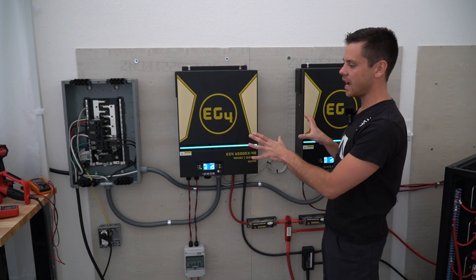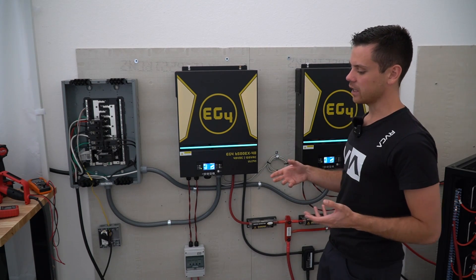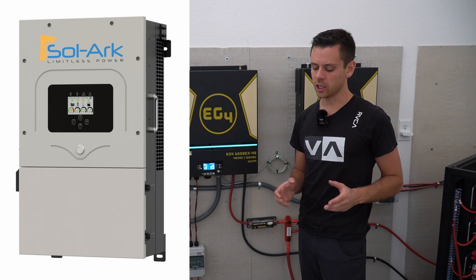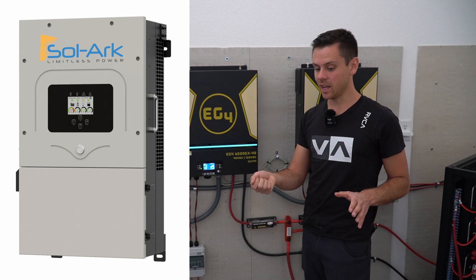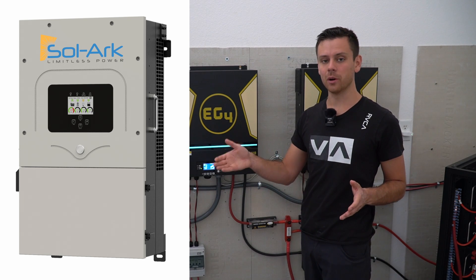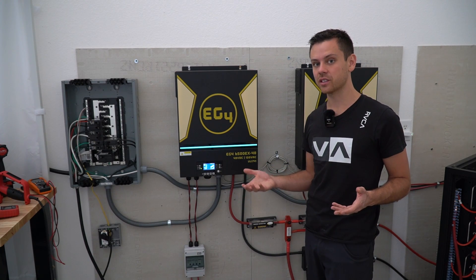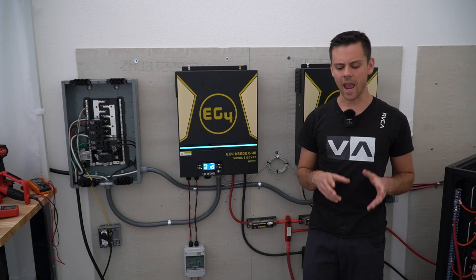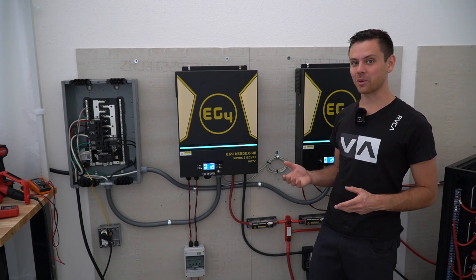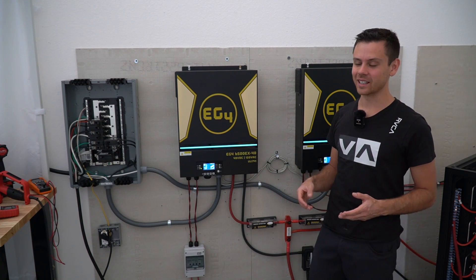For off-grid use, these are fantastic — I love every type of LV6548, including these. But if you want to pass inspection, you need to spend the extra money and get a Sol-Ark. You will have zero headaches: it has rapid shutdown, a transfer switch built in, and Sol-Ark's customer service has engineers that can remotely change the settings. The support, certifications, and UL listing are fantastic, and that inverter is approved by California — which is very difficult to achieve. It does cost three or four times as much as these units, so if you want to pass inspection, you need to pay the money and get it done right.